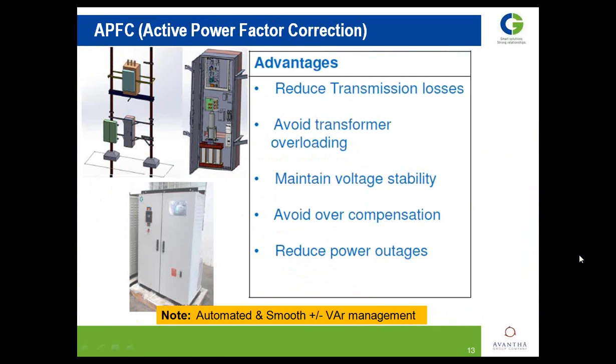All of you know APFC, automatic power factor correction. Instead of a conventional one, can I have an automated and smooth one where I can vary in an active way, and where I can put it on 11 kV poles or in a control panel, and based on the need or the problem, I can put it wherever the problematic area is? It means instead of putting it on the incoming side, can I put it on the outgoing side, so that my load side is getting mitigated, indirectly the impact on the source side or the purchase side is getting managed or met. That's the theme of the slide, and it's fully automated and smooth for both positive and negative VAR management or VAR compensation.